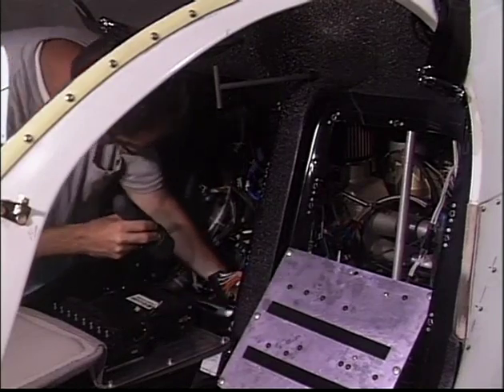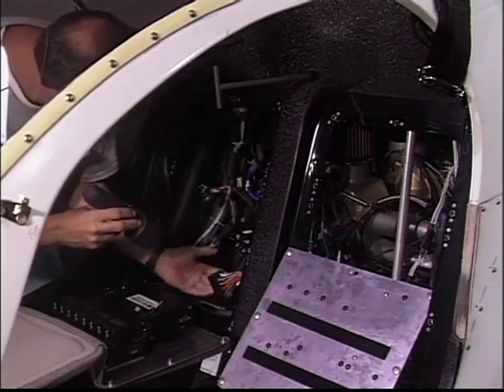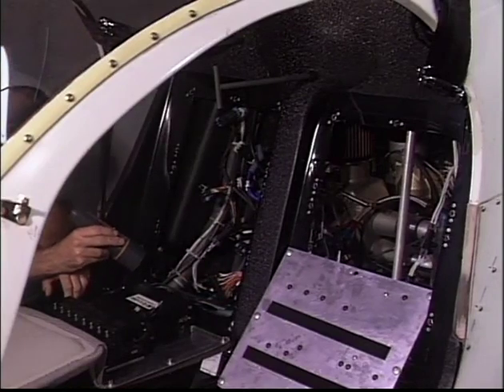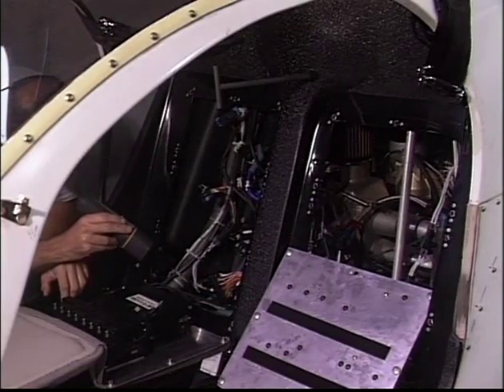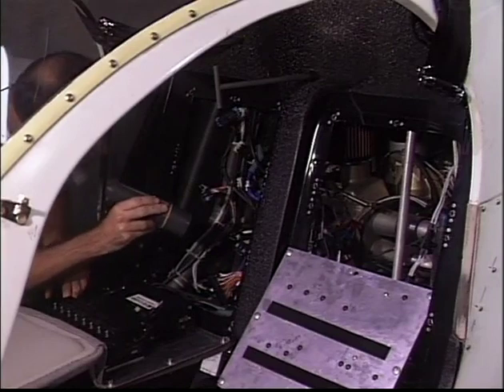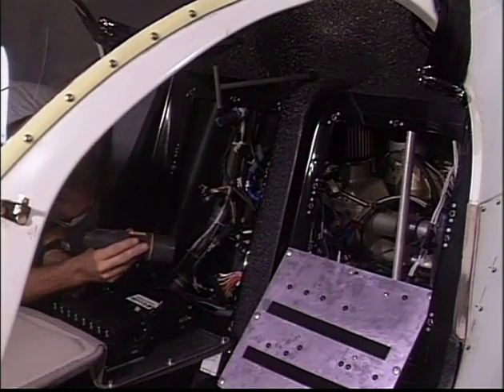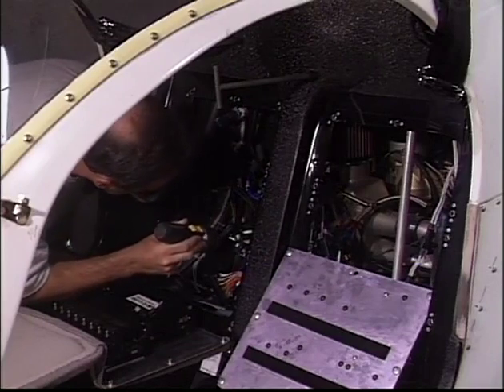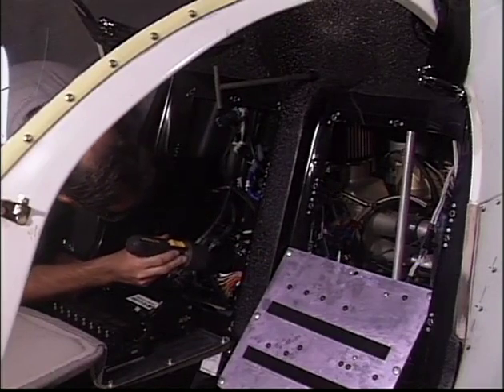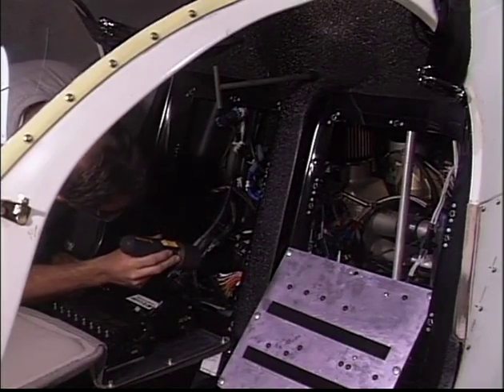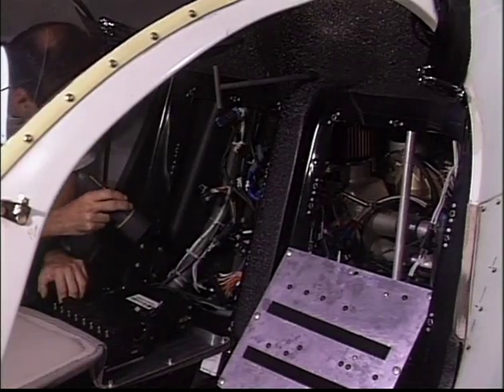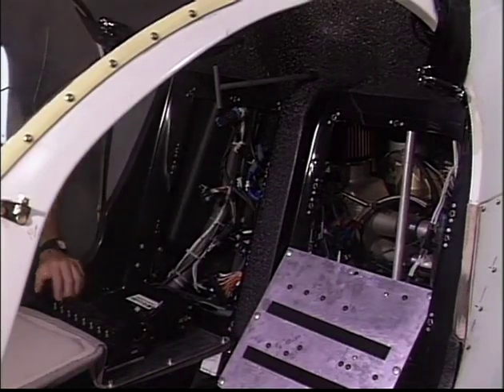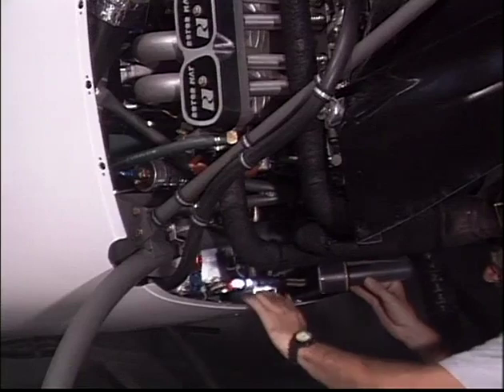Immediately turn off the fuel pump and fuel valve if a leak is detected. If a leak is found, pressure will remain in the system after the pumps and valve have been turned off. Slowly disconnect the hose at the spot of the leak and be prepared for fuel to spray from the connection. Turn on the second pump. Carefully check for leaks.